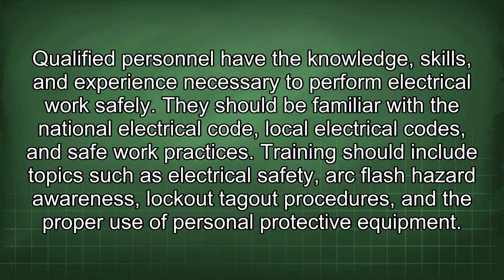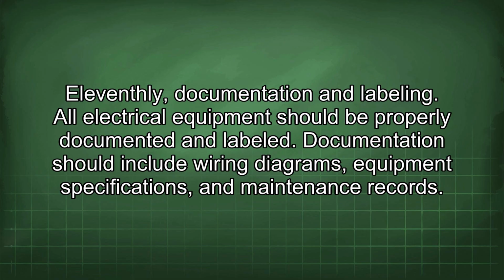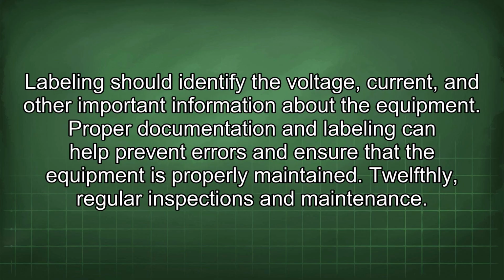Training should include topics such as electrical safety, arc flash hazard awareness, lockout-tagout procedures, and the proper use of personal protective equipment. 11th, documentation and labeling. All electrical equipment should be properly documented and labeled. Documentation should include wiring diagrams, equipment specifications, and maintenance records. Labeling should identify the voltage, current, and other important information about the equipment. Proper documentation and labeling can help prevent errors and ensure that the equipment is properly maintained.